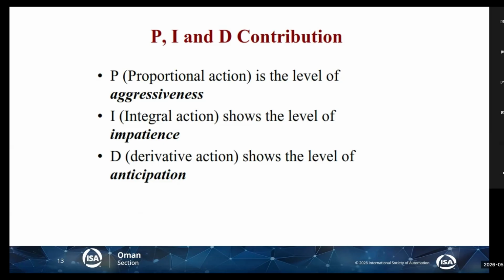And integral shows the level of impatience, how impatient the controller is. It can be represented in seconds or minutes, and this is very important because in some DCS, when you tune, if the integral is in seconds, that means it is a very small number. If it is in minutes, then 2 minutes is 120 seconds. So you should first see the unit, because sometimes it's in seconds and sometimes it's in minutes.